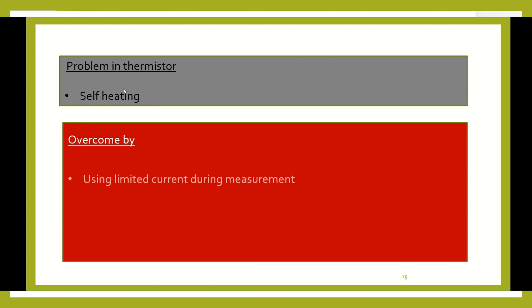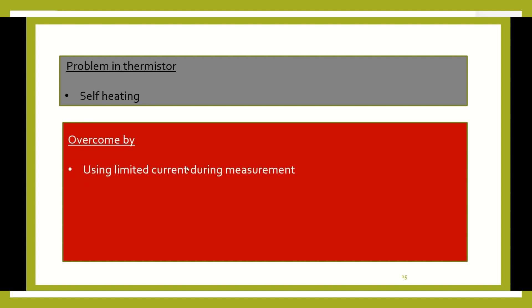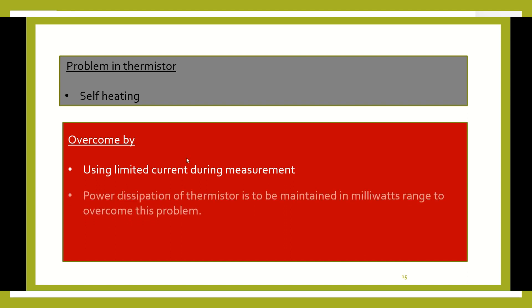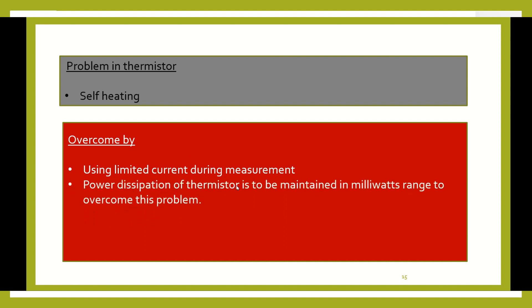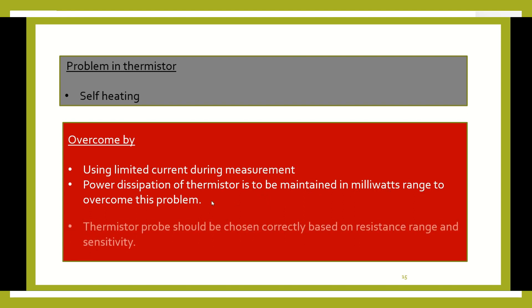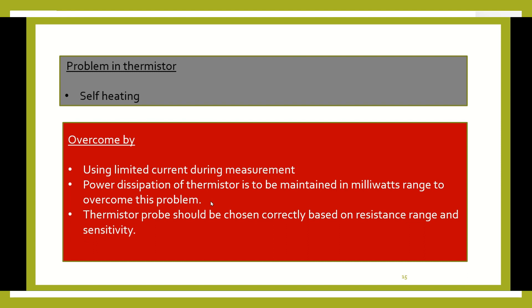A problem with thermistors is self-heating — the device may automatically heat up during use. To overcome this, we can use limited current during measurement. The second option is to maintain the power dissipation of the thermistor in the milliwatts range. We also have to choose the thermistor probe properly based on resistance and sensitivity. By doing this, the self-heating problem can be avoided.